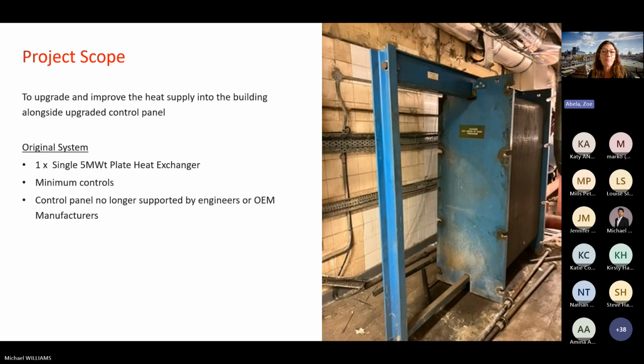The scope was to replace the old plate heat exchanger. This was last upgraded in 2008, and we were upgrading it with a twin plate heat exchanger with upgraded controls, replacing an old PLC controller which was no longer supported. Thankfully there was a little floor space in the plant room, a rare luxury for buildings in the city, which we were able to use to house our new heat exchanger.